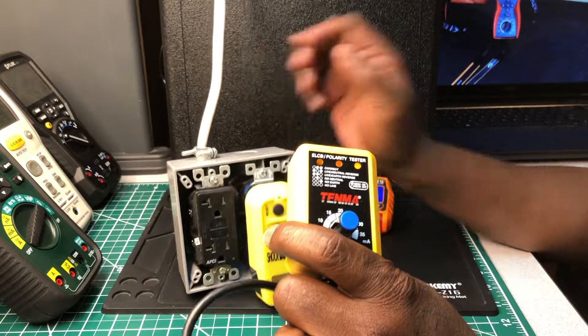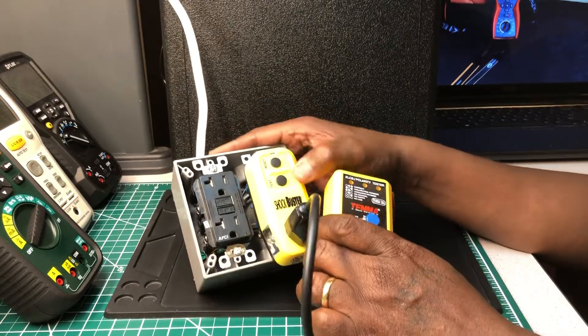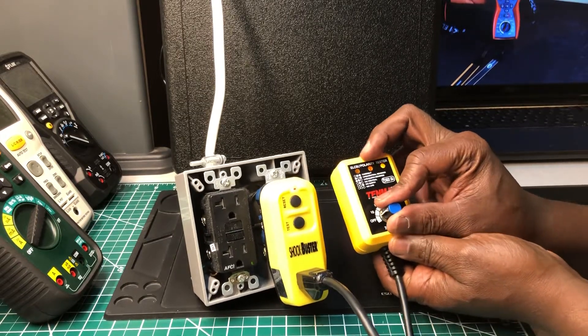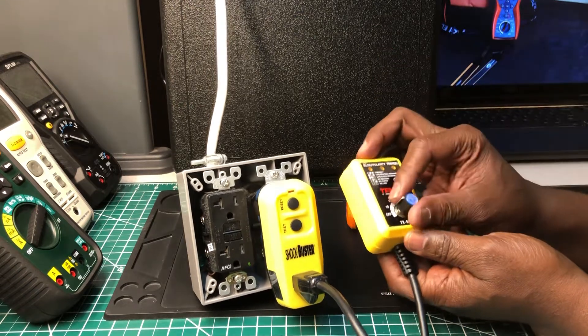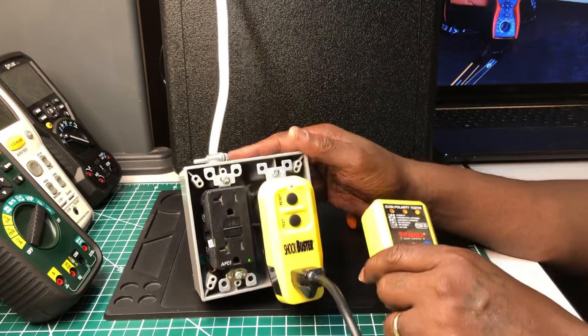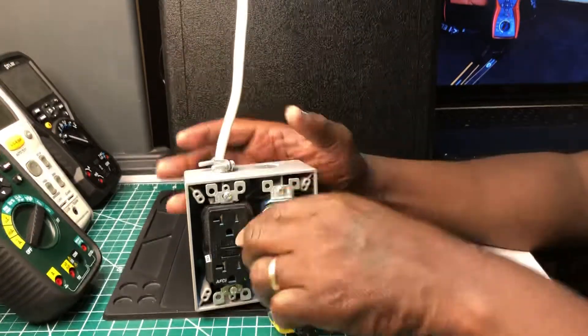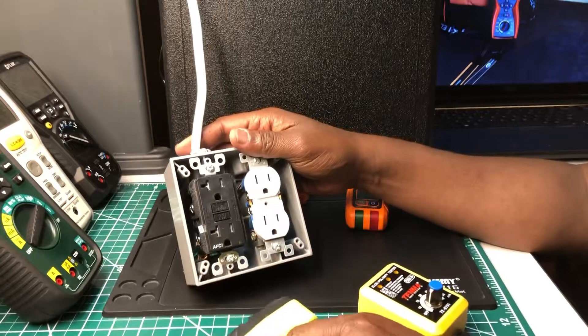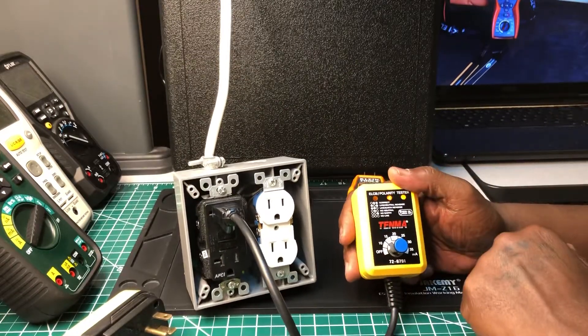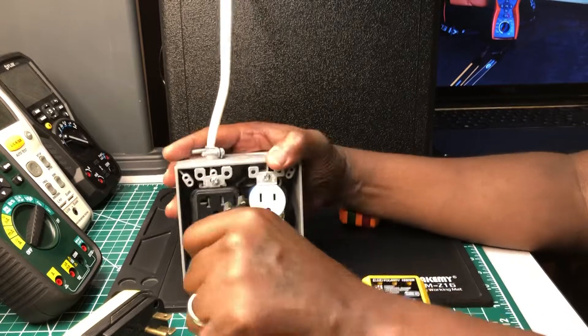It gives you two lights when lit up, telling you it's correctly wired. You just turn this dial right here and that should make it trip — and there it goes, it tripped. I'll reset it again, turn it to 10 milliamps, and it trips. So it does work. I didn't try it on the AFCI — I didn't think it would trip it, and it didn't. It's just for the GFCI.